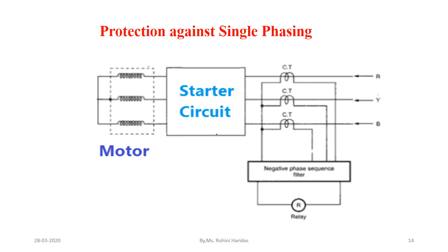CTs are provided in each phase and their secondaries are connected to a negative phase sequence filter. When the supply is balanced, there are no negative sequence components and the relay will not operate. Whenever there is unbalance in supply voltage or single phasing conditions, negative sequence components will flow, and if the value exceeds the preset value, the relay will operate and send a signal to the trip circuit to isolate the induction motor.